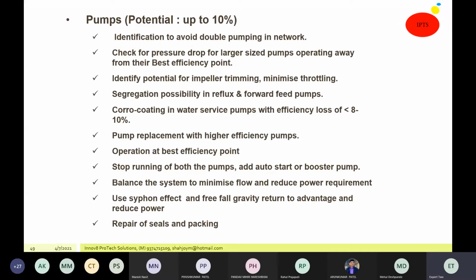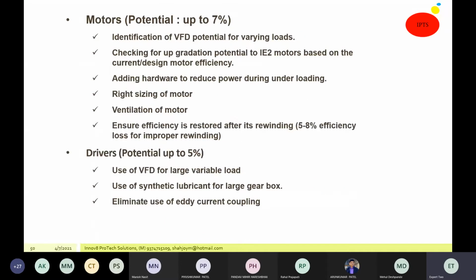Motors, because of the variable load, if you have a variable load, look for the VFD. Check for upgradation potential. Now you see there are several high efficiency motors available, and these are all termed as IE2, IE3, IE4. Now people are talking about IE5 also, but in industry we are using IE3 and IE4 nowadays. If they are old motors, they are all IE2 or IE1. So there is a possibility of improving the efficiency by replacing the motors with high efficiency motors.